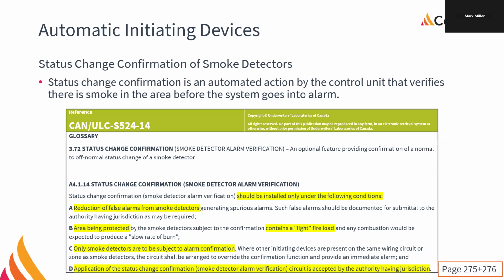And again, permission is only provided by the authority having jurisdiction. Because what happens is the panel gets reconfigured for status change confirmation. So you put smoke to a smoke detector, the smoke detector goes, oh, there's smoke. And it tells the panel, oh, we got smoke, right? Because it's gone into alarm. The panel goes, well, I'm not convinced. I'm going to wait 30 seconds and then reset you and see what you say. Right, so the panel will wait 30 seconds. It will reset the circuit and see if it's still in alarm, right?